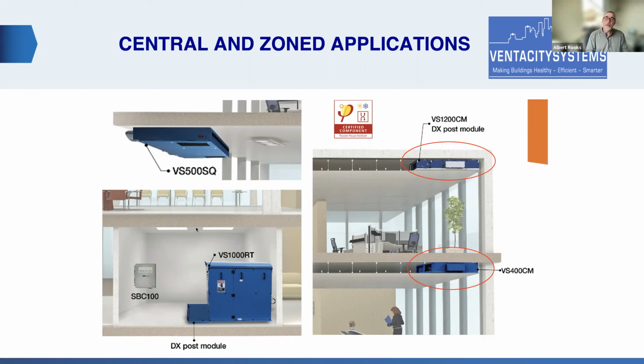So this is a case saying, okay, we've got ways that we can deal with individual small rooms and multiple rooms, but all these buildings have larger spaces and they have corridors. So we've got to have a way to deal with that. And I like this slide because in the retrofit world, maybe on the right-hand side, we can fit a 14-inch thick piece of equipment in a ceiling, leave it exposed or cover it, whatever we want to do, add some ducting, and we could take a corridor, take per corridor on the height of the building and treat it with a 400 CFM unit or a 600 or a 200 or whatever number we want, and treat them that way.